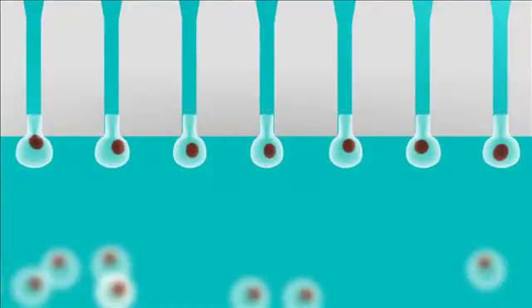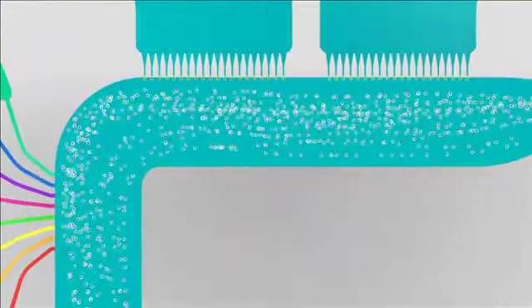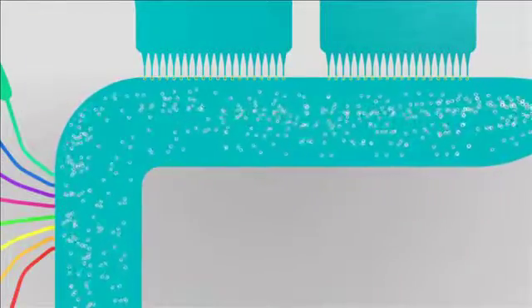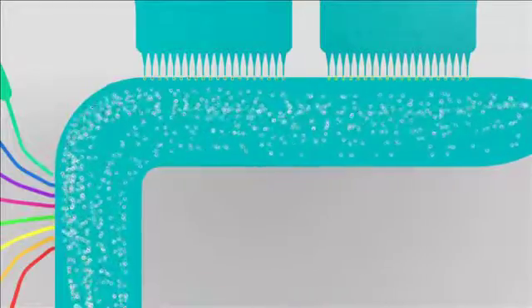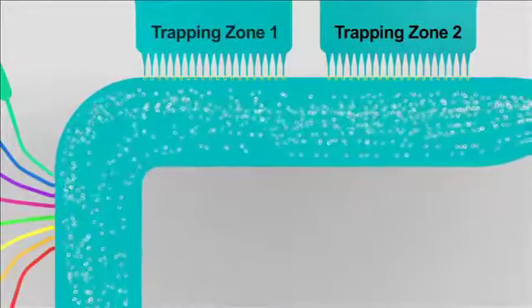Once the cell is attached, whole cell voltage clamp is achieved. The IonFlux system uses ensemble recording to provide maximum success rates. Each trapping zone captures 20 cells which are used to make one patch clamp recording. There are two trapping zones per experimental pattern.